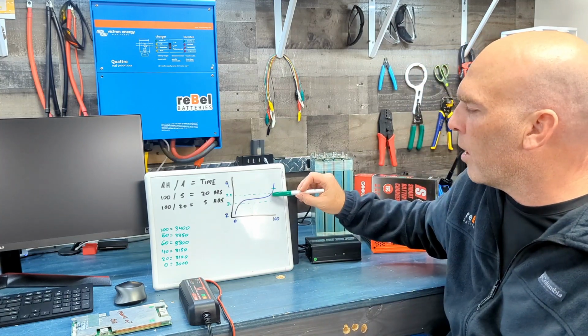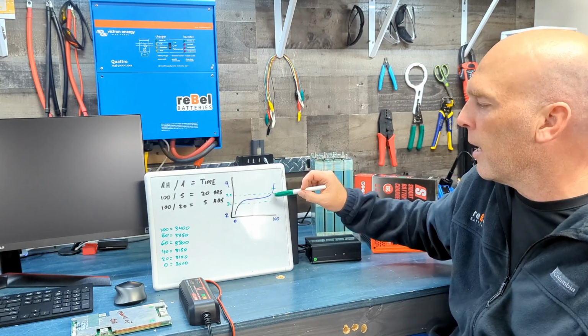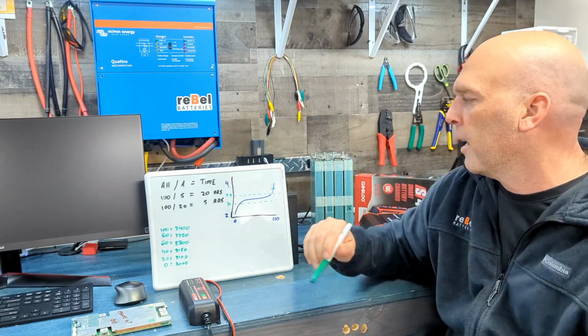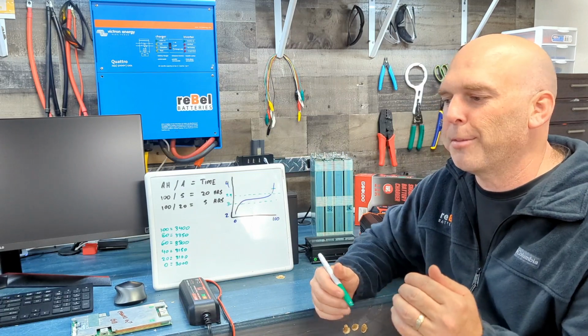I still have customers come back and say, no, I don't believe that, it shouldn't be saying 90%. I try to explain, you really need to look at the voltages. Anything over 13.35 and you're beyond what's called the knee—you're past it, or right at it—and you're not going to get but maybe 1 or 2% more in there, even if all the cells were perfectly balanced and they all went up to 3.65 exactly, hitting 14.6 volts perfectly. You'd still only add maybe 2% from 13.35 to 14.6—just 1 to 2% capacity.